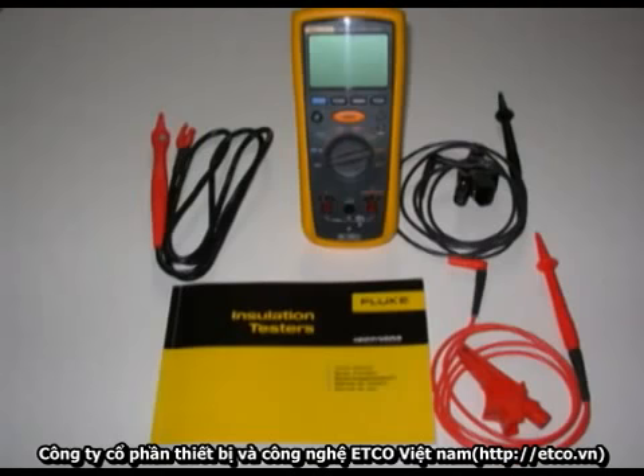The positive and negative leads are extremely stout and sharp to make a good contact with a case or a coil. There are also alligator clips for the extended 10-minute polarization index test, or PI test. The lead to the left is 3-pronged and has a button in the handle. This is used for ohm readings, PI tests, DAR tests or dielectric absorption ratio tests, and insulation tests. You can also use it on the other side as an ohmmeter. It is a remote button that can be used instead of pushing the button on the meter.